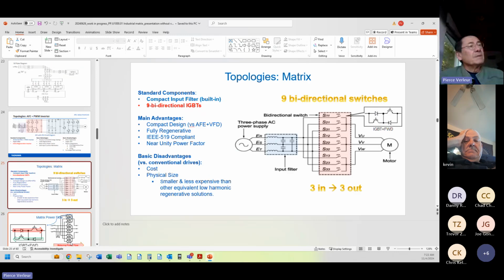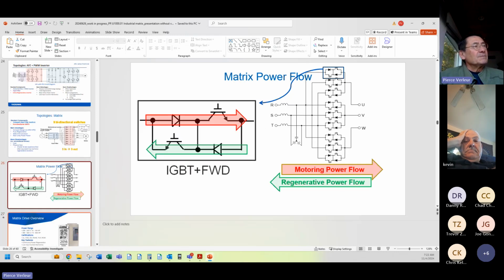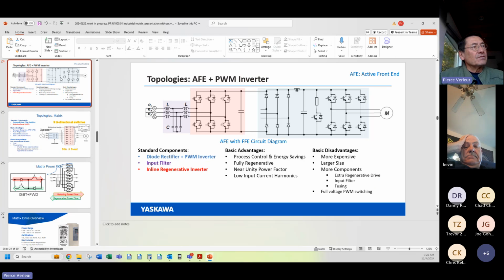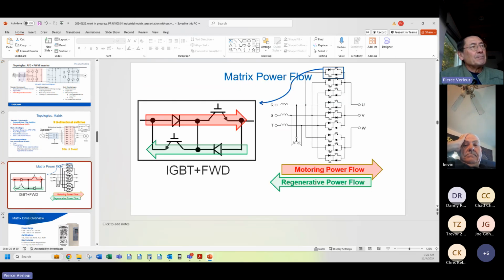And then we have matrix drive. And the matrix drive, this is a better diagram of the matrix drive, is basically massively simplistic, a huge change from this. Number of parts, and it's just basic simplicity. Matrix drive is nothing more than 1, 2, 3, 4, 5, 6, 7, 8, 9 two-way switches. There's no DC bus. There are no capacitors associated with the DC bus. There's just a direct switching connection.